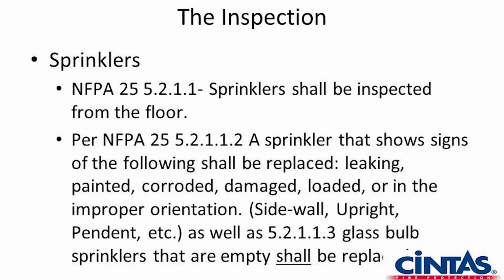If something has bumped a head and cracked that glass bulb, which is very rare but does happen, the liquid will be gone. There will be no fluid in that bulb, and if a fire were to start up underneath that sprinkler head, it's not going to discharge. Glass has a melting point somewhere around 2,500 degrees Fahrenheit, so you can imagine if your building is that hot, you've got some major problems, and that head still hasn't discharged.